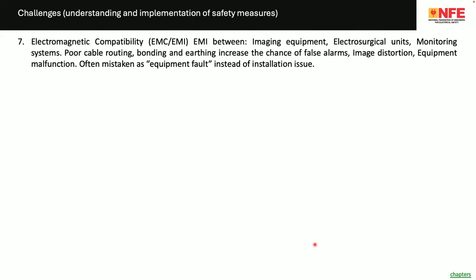Electromagnetic compatibility, another big issue in hospitals. Example, electrocautery machine. In several operation theatres in India, I have visited at least 50, 55 such operation theatres. Whenever the electrocautery machine works, the challenge starts. Sometimes the display of the next equipment is malfunctioning. Sometimes the display is off.